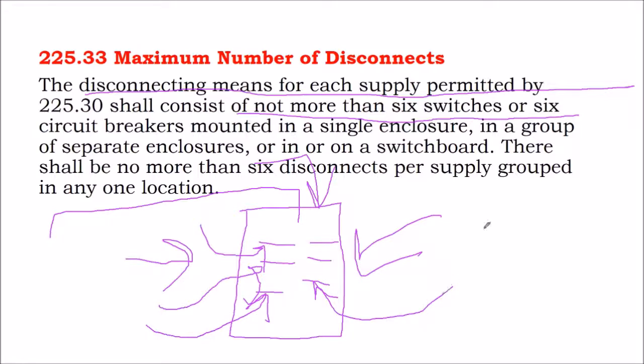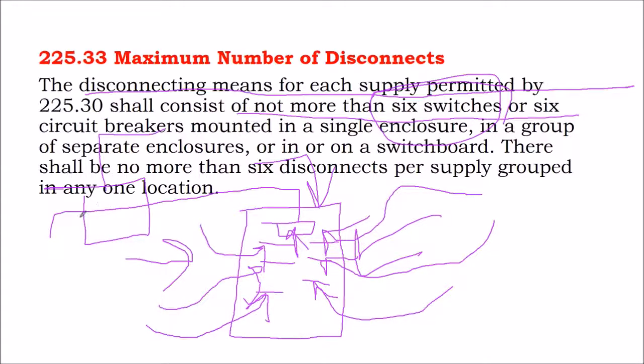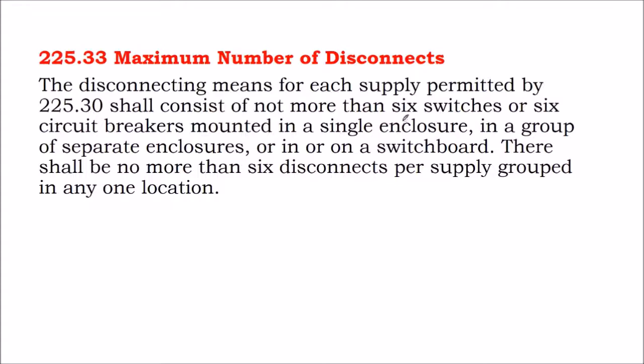Now, what happens if I have 7 inverters or microinverter branch circuits or what have you onto this panel? And so now I no longer have 6 switches, I have 7 switches. Well, at that point, you put in a main breaker, and that becomes your single switch disconnect. Or alternately, you put in a knife switch disconnect with a fuse, and that would serve in lieu of the main breaker. But in either case, you have your main overcurrent protection device and switch where you can flick no more than 6 switches to fully de-energize that supply.